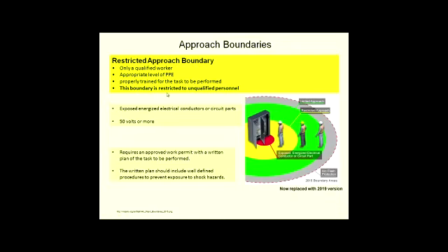This boundary is restricted to unqualified personnel. So if you're not qualified to do the work, you have no business being there, okay? Or anybody. So exposed energized electrical conductors or parts, 50 volts or more. No? 50 volts or more.